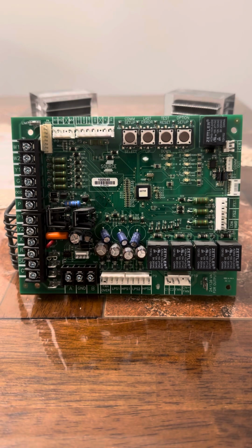Even sometimes if it's a highly resistive coil on a contactor, it can trigger something like this where it's tripping the limit. Okay, so that's obviously if you've already exhausted all your other options in terms of overheating and tripping the limit. Now, I've seen situations where the time delay for the blower fan on these Simplicity boards goes bad, where the fan will turn off too quickly after a heat cycle, without cooling down the heat exchanger. That's the blower off delay.